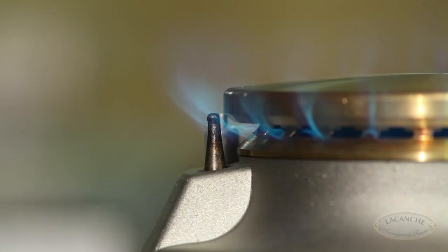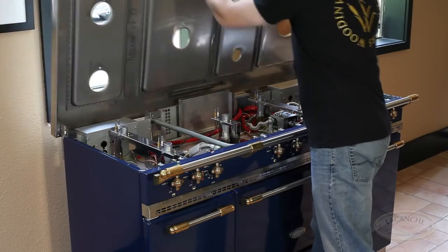The tip of the thermocouple probe should remain in contact with the flame even at the low setting. If necessary, readjust the probe and lock into place. Lower and reinstall the range top.